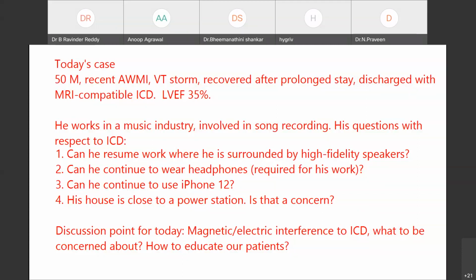As I said a minute before, nothing is all or none. And similarly, the interference is also not 100% or 0%. Many of the interference, let us say the total interference is 3% in the reported incidents. And out of this 3%, you will be surprised, less than 0.5% are really things which would cause life-threatening problems. Most of them, what do they cause? They cause a change into an asynchronous mode. Again, it just changes from a VDD or a DDD mode to a VOO or DOO mode. That means it continuously paces. No problem at all. The only thing is you need to reprogram it, but there is no harm to the patient.